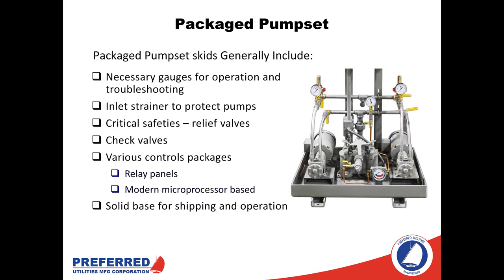An internal relief valve may not be appropriate for transfer pumps, but you will see it on things like the polishing skid or return pumps of the day tank. The package pump set offers many advantages and is typically how we see these in the field now. While there are still applications where equipment is designed piecemeal with the contractor purchasing each part, the advantage of having one manufacturer or sole source for the skid is that necessary safety items — the relief valve, gauges, strainers — are all sized properly from the get-go, coordinated at the factory, and can require a factory test before arrival at the job site. That includes the controls as well, which we'll take a closer look at later.